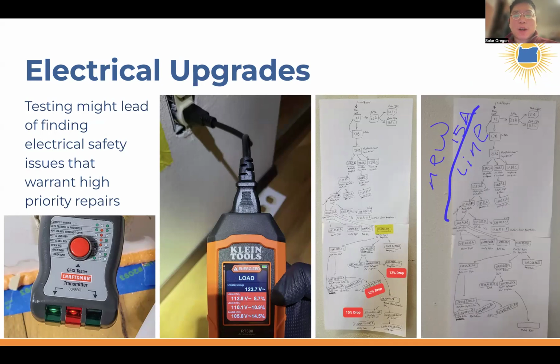It's no wonder why at the receptacles near the end of the line we're getting incredibly high voltage drops. So before air sealing and insulation of this home, a new electrical wire was run to break up this daisy chain so that the receptacles near the end of the line get much less voltage drop.